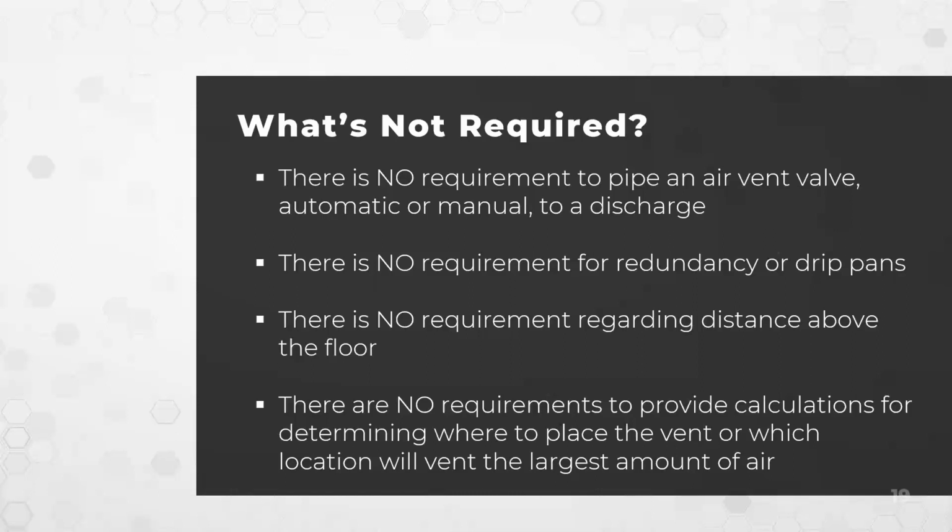You're not required to have them a specific distance from the floor. I've seen some specifications where they said the air vent shall be located at the highest point. Unfortunately, the highest point of a building may not actually be the best place to locate the air vent.